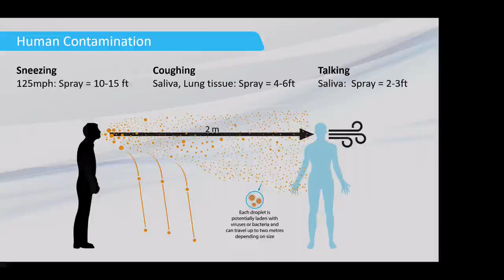So, not wanting to reinvent the wheel, we looked at the market again and saw that there were mobile filtration systems being advertised. So we obtained one and carried out some tests on it, specifically air smoke visualization. So we squirt smoke into the air and look at what the air is actually doing. And what we found was that while these filtration units had fans and filters operating at maximum efficiency, H14, and the fans were pumping enough air to theoretically completely change out the air approximately 12 times an hour, what they're actually doing is just circulating air down one end of the room, doing nothing to capture, keep buoyant, and extract particles from the other side of the room. So effectively, we're finding that 30 to 40% of the room was being cleaned down, and the other 70% was not capturing those. Yeah, it was just diluting.